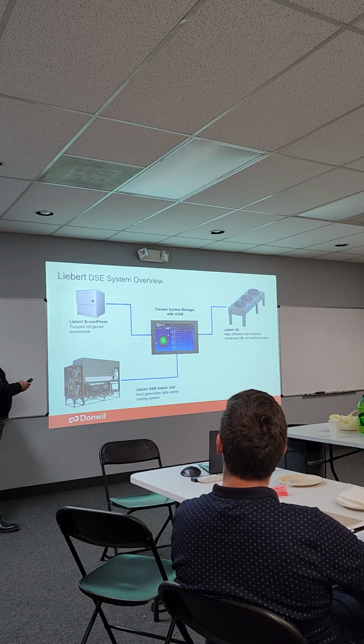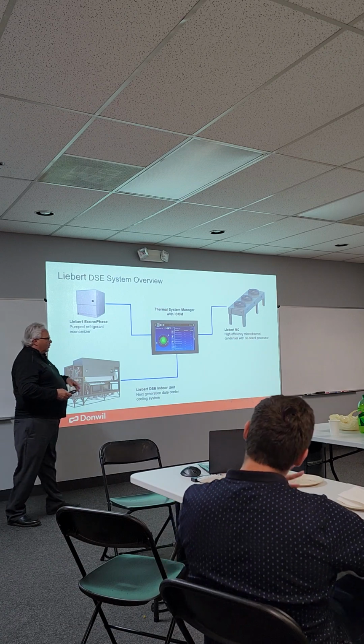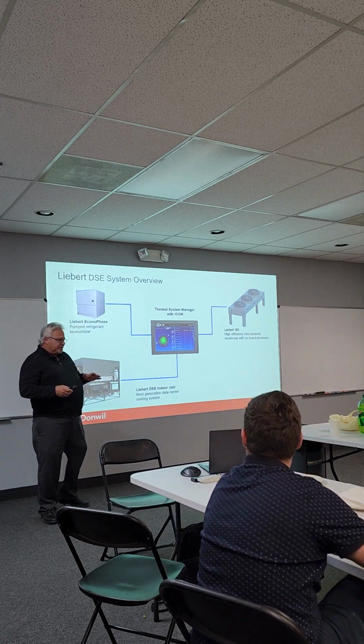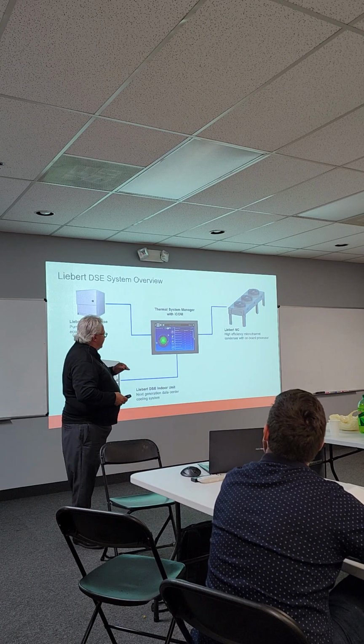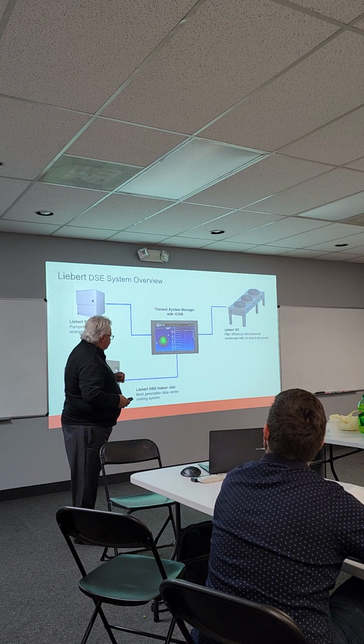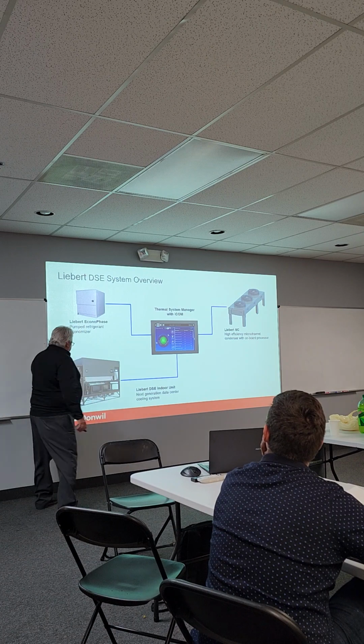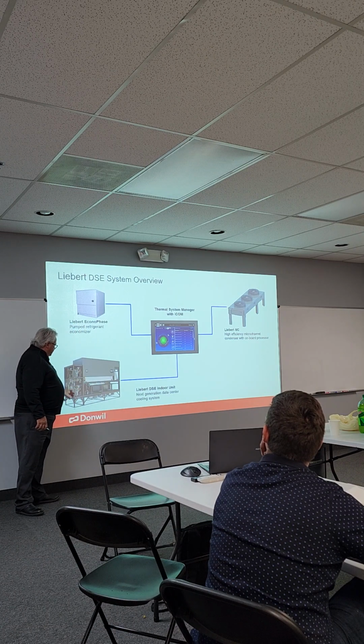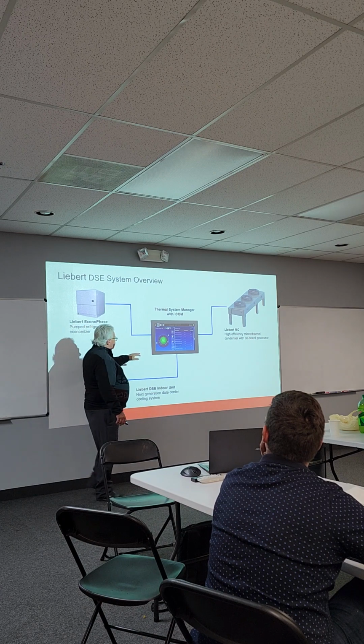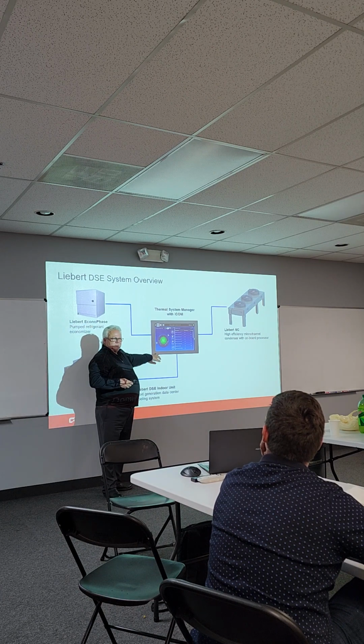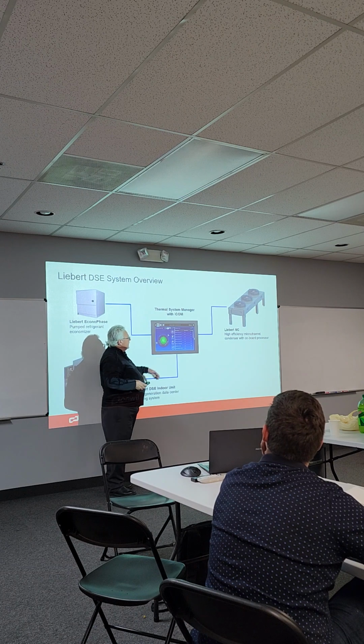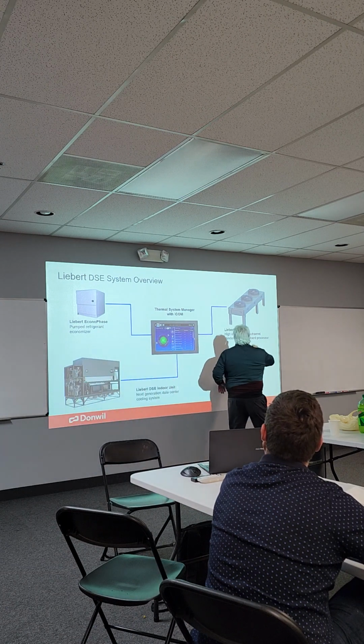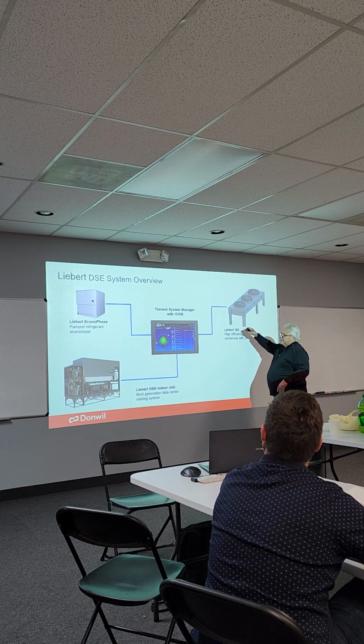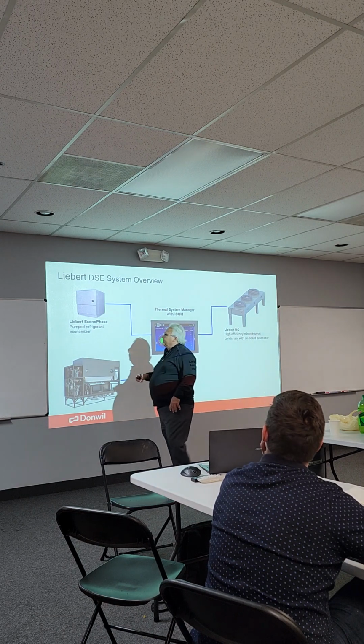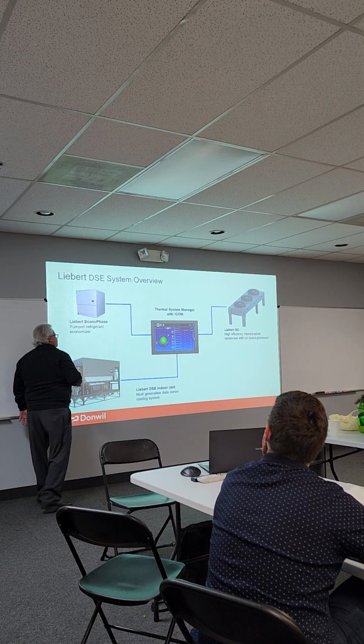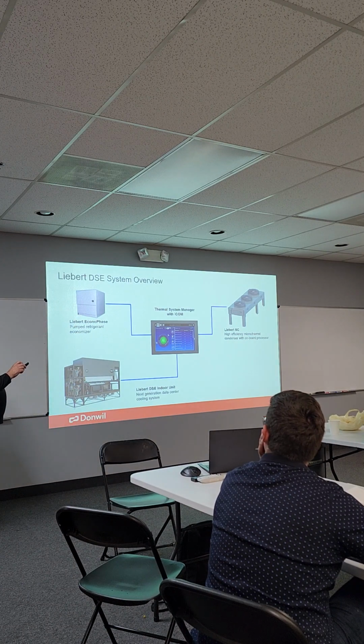All right, so let's go back, and now that I kind of got off the beaten path, let's go into this DSE system. So remember I told you that we're kind of looking for better economization, so we can economize at a better temperature than 35 degrees. So here's your basic indoor unit. Then you have the iCOM control, which you guys are gonna see at the post office. Then you have the microchannel condenser. And then there's one piece that we're adding in here, which is the EconoPhase pump. That is pumping liquid refrigerant.